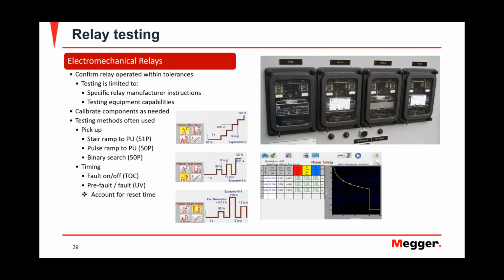To do timing, you could do your fault. Some tools will even have the graph and the curve, and they will show you how much time it should take for the relay to trip. You could use what they call a pre-fault or fault, where you have a pre-fault with nominal values, and then you apply the fault to measure the time that it takes to trip. And one thing to keep in mind is, especially if they have the induction disk, make sure that you allow time for the relay to reset. Sometimes when you're doing the timing and you test 2 times and then immediately you test 3 times pickup, if you don't allow time for that disk to rotate, your timing is going to be off. So one thing to keep in mind when you do this type of test is at least on certain manufacturers, it's called the reset time for the relay.